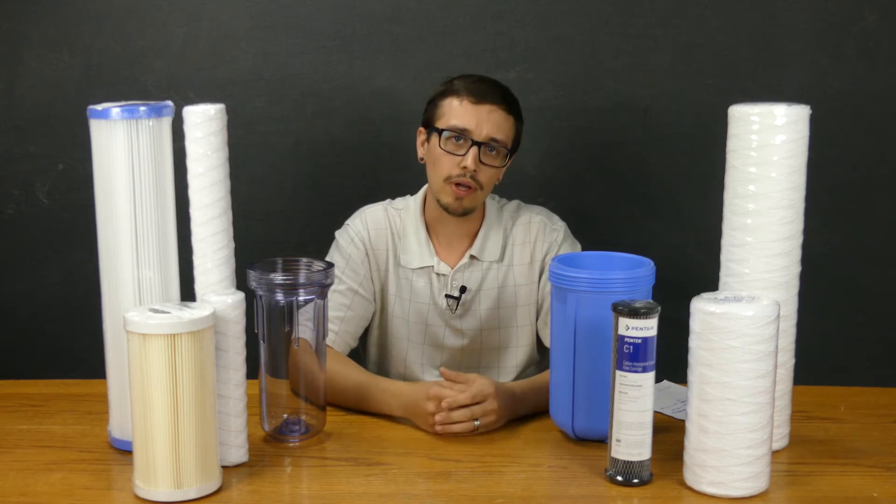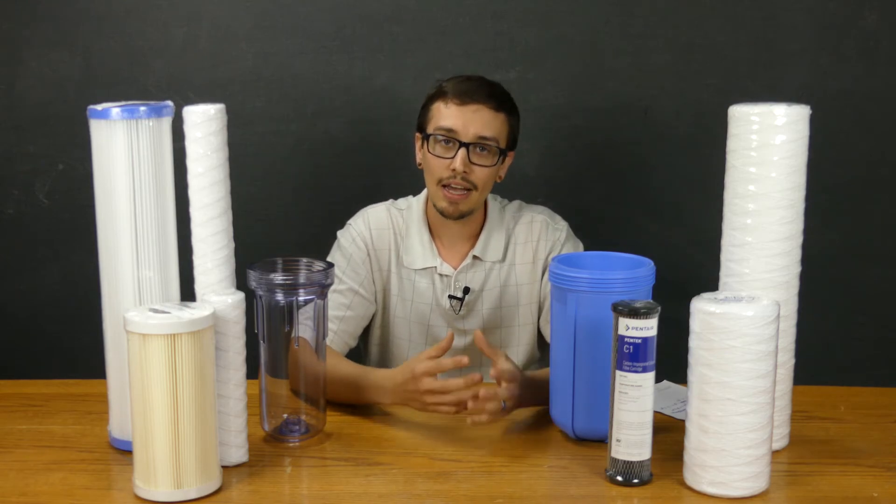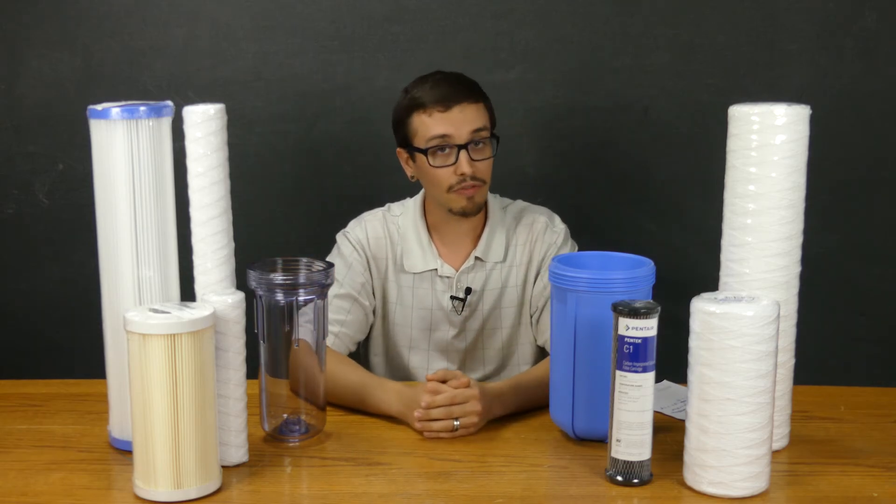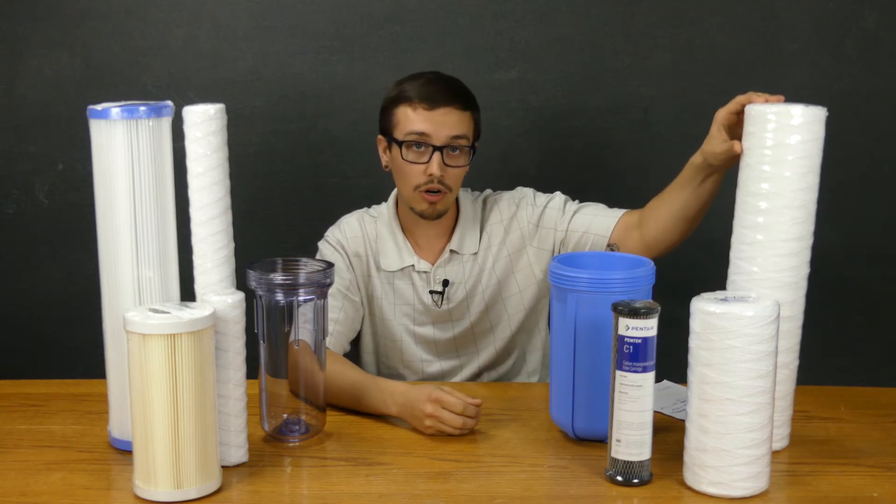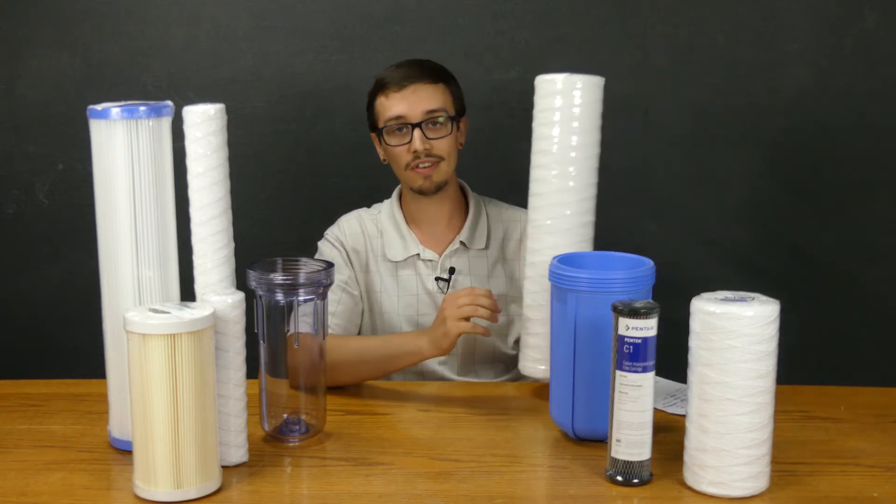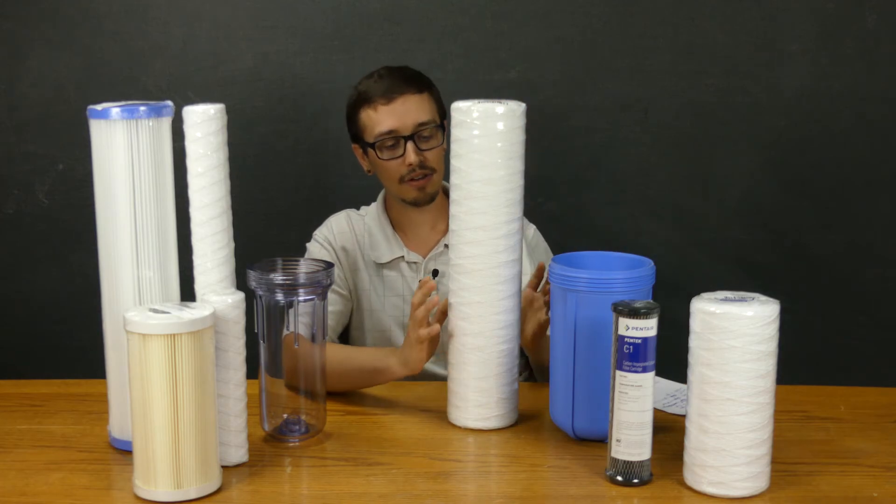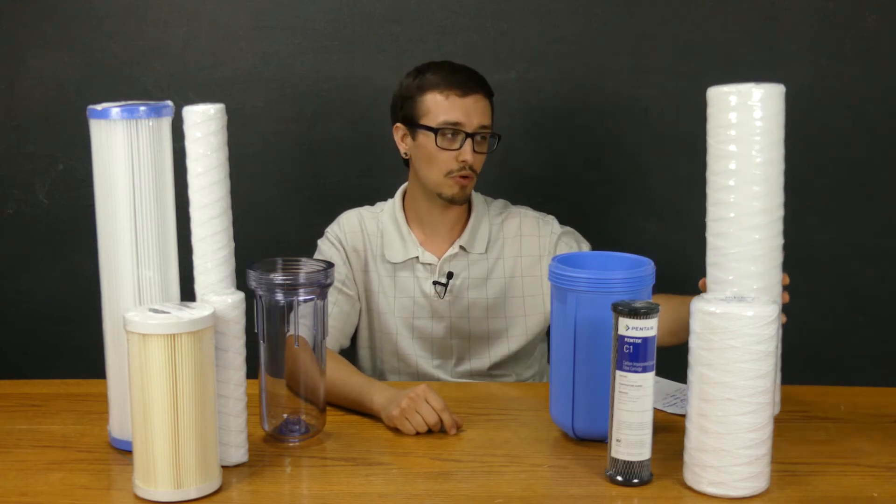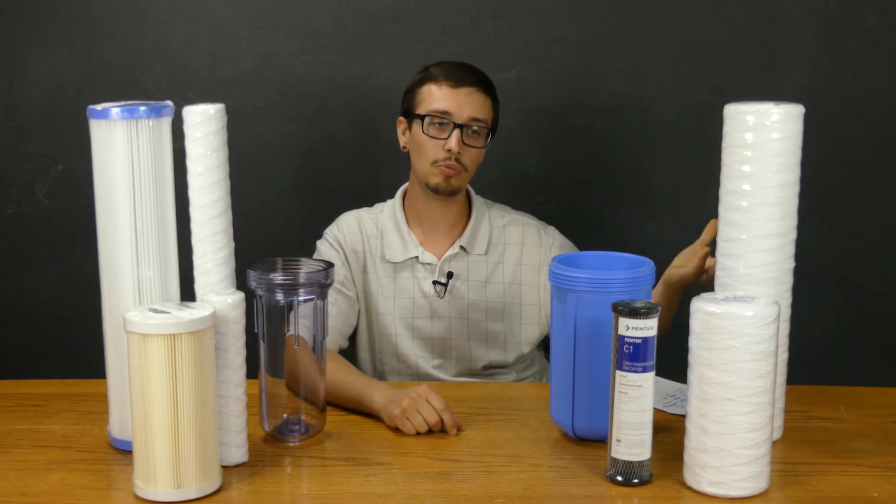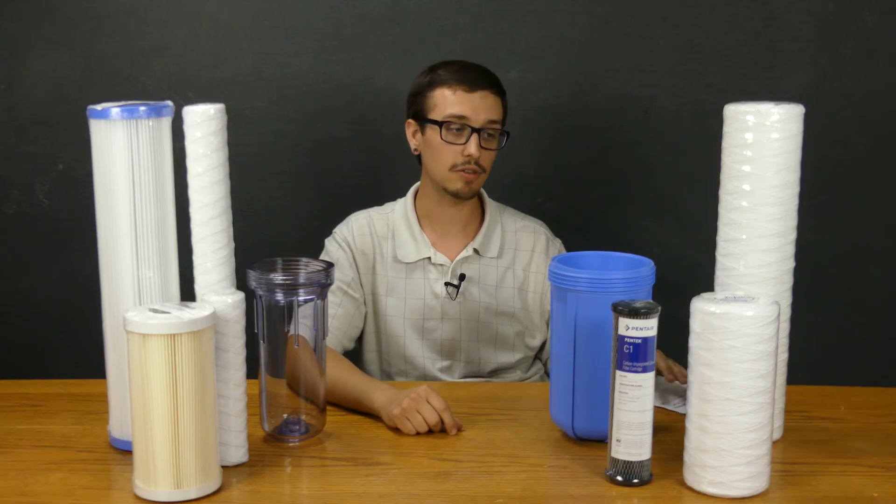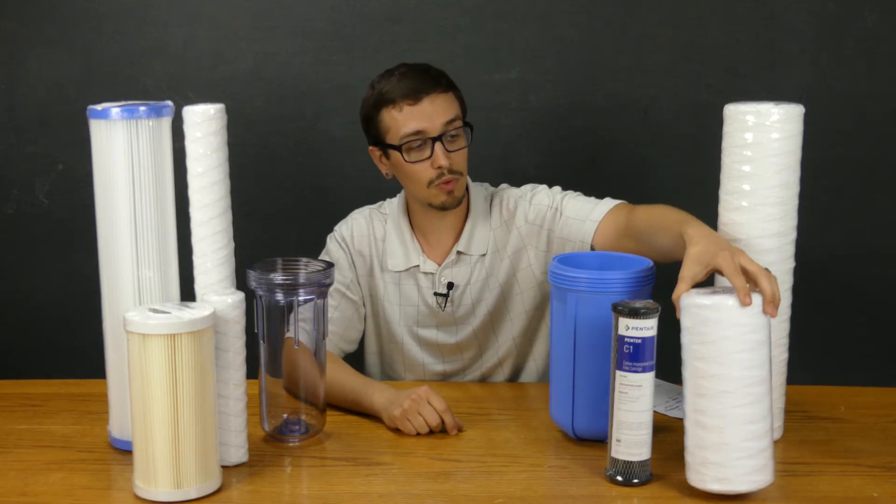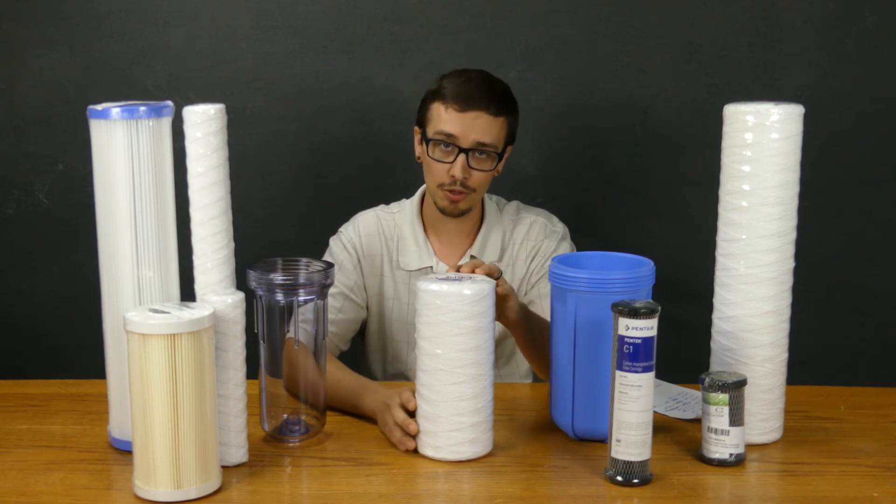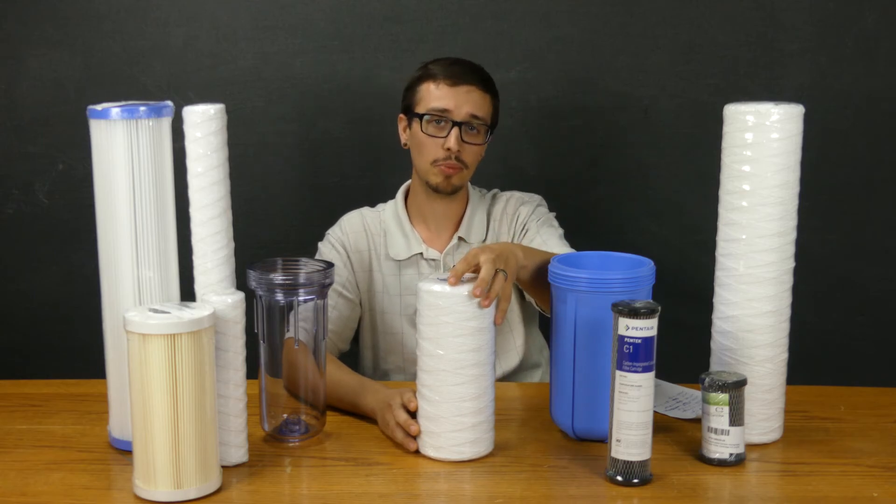Let's get more specific and talk about some of the actual flow rates and pressure losses you could expect when looking at these different filters. The first one is this large string wound filter. This is a 5-micron string wound filter. A filter like this you could expect to get upwards of about 15 gallons per minute without experiencing too much friction loss. The smaller string filter is rated at about 10 gallons per minute before that pressure loss starts to become an issue.